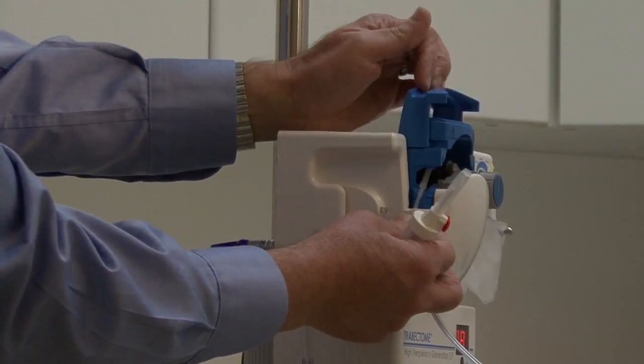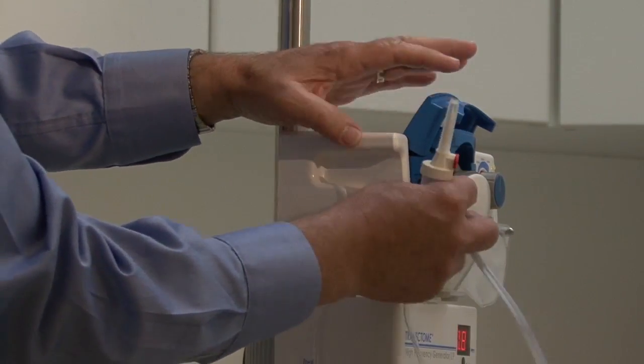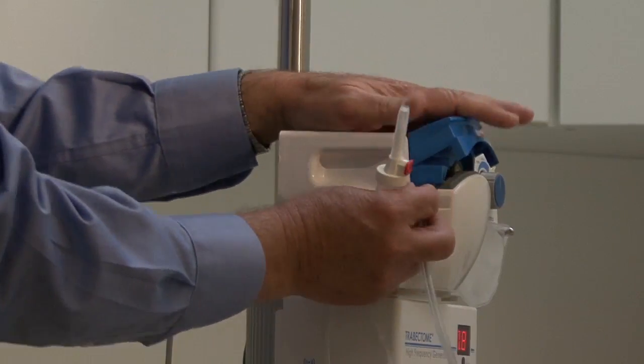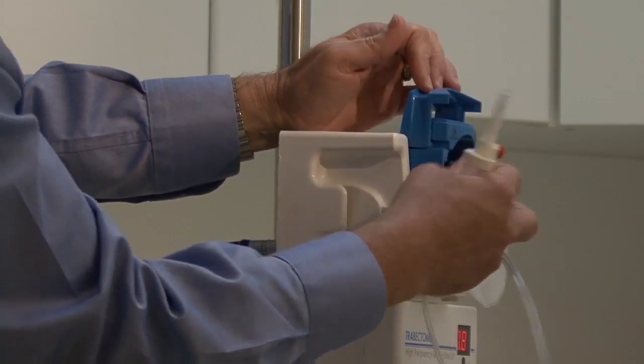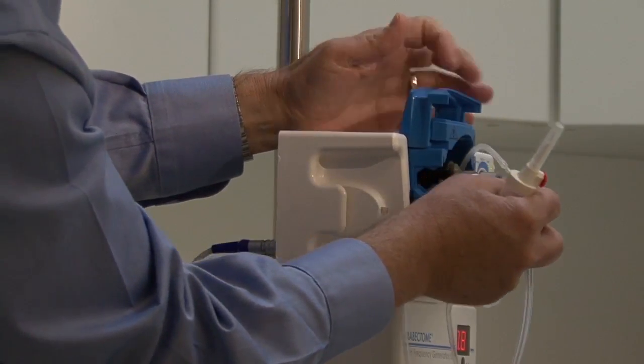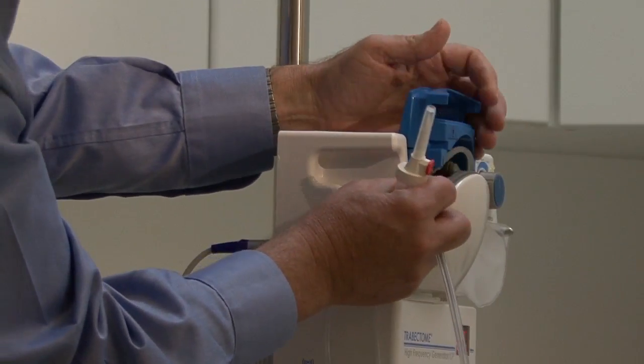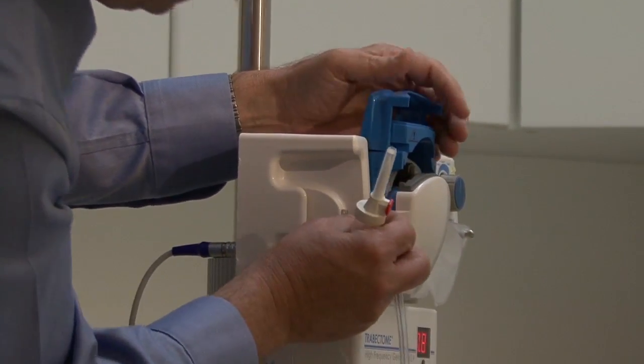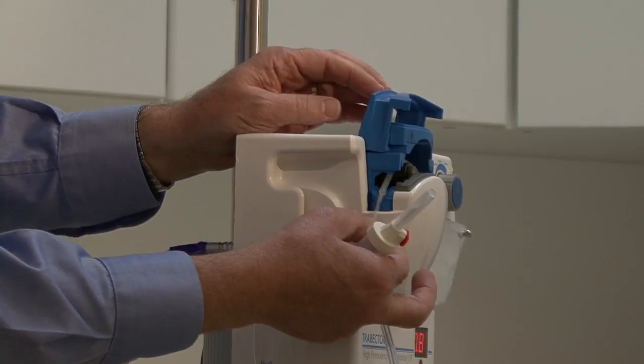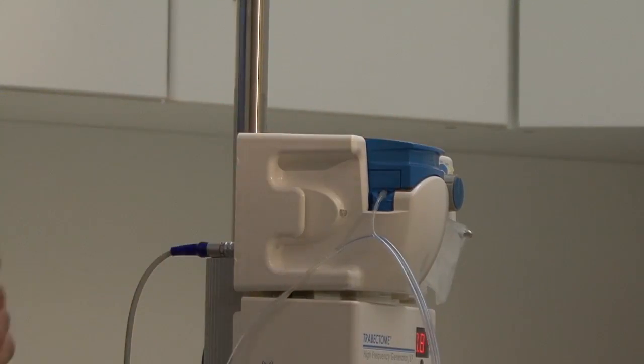The only thing I want to point out is if you go to close the pump and you don't see this little fitting, it means there's something wrong. It probably means the tubing's behind the rollers or just not properly positioned. So go ahead and open it up. Just lay it right across the middle of those rollers, the pump tubing. Stretch it a little bit so when you close it, the little fitting should be showing just like this, and it's all ready to go.